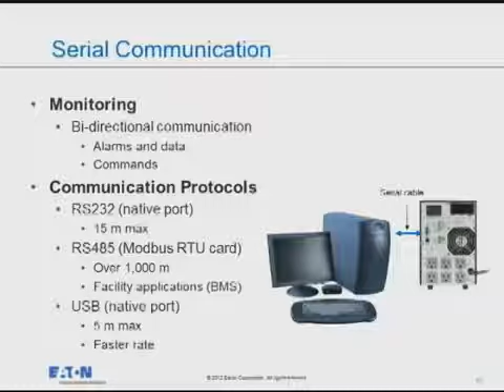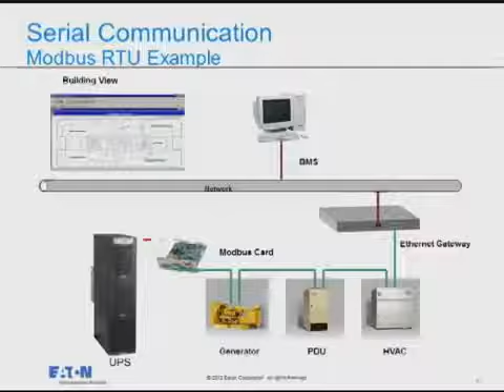We also get into a Modbus RTU card. Many UPSs today, because of the criticality of communications, have a card slot where you put in a communications card applicable to the environment. In this case, we'd take a Modbus card into the UPS and connect it serially onto a Modbus network, piggybacking onto the generator, PDU through a gateway onto our Modbus network. Now I'm using a building management system in the building view, collecting the data, uploading register maps, mapping it all out, and bringing it into the overall system.